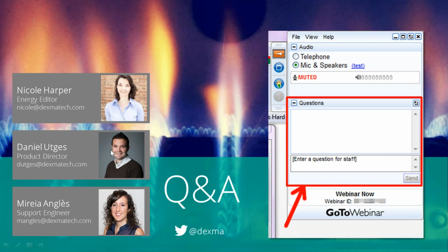Dexcell receives pulses or cubic meters. In order to obtain kilowatt hours, you need to consider the higher heating value or the lower heating value. These values are often given by a supplier once a month. Yeah, exactly. So the question is about how to maintain those numbers that can change every month. Right now, what is doable is to manually change that value inside the software, but you have to remember to do it. So there is nothing to change it in real time? Not yet.